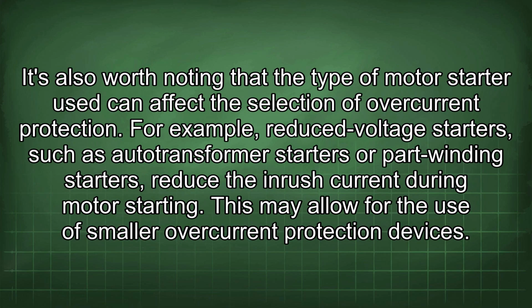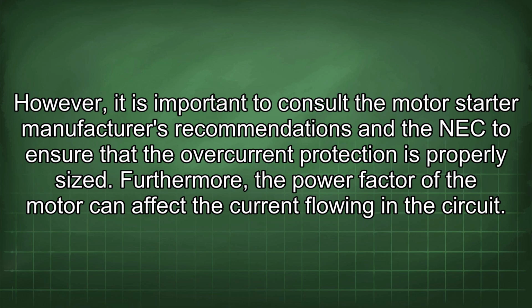It's also worth noting that the type of motor starter used can affect the selection of overcurrent protection. For example, reduced voltage starters, such as auto-transformer starters or part winding starters, reduce the inrush current during motor starting. This may allow for the use of smaller overcurrent protection devices. However, it is important to consult the motor starter manufacturer's recommendations and the NEC to ensure that the overcurrent protection is properly sized.